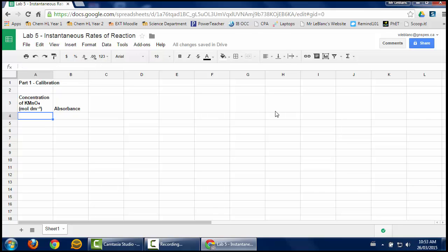So I need to be able to interpret the graph. SparkVue won't auto-adjust the graph for me. It won't, let's say, just output concentration versus time on the graph. It will give me an absorbance versus time graph, so I need a way to convert all the absorbance readings into concentration readings.